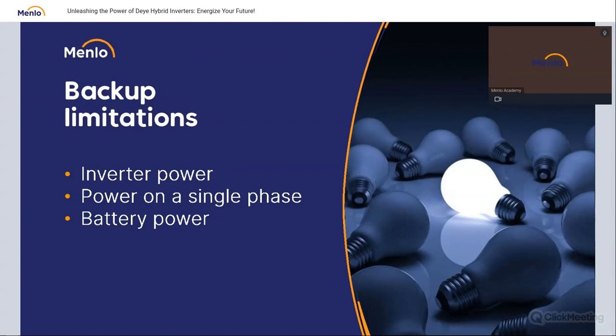Our client, your client, has PV panels, has a hybrid installation, has batteries. They feel safe because they have this emergency power supply thanks to the hybrid inverter and batteries. They start using it when the grid is off and the system turns off. They are angry, they are mad. So it's good to know what limitations are over there to tell the customer, you cannot do that in off-grid mode, or to get all the requirements from the customer and plan it in such a way that if the customer works as he promised, as he required, you as an installer, your installation will survive and work perfectly fine. Why am I telling you about it?